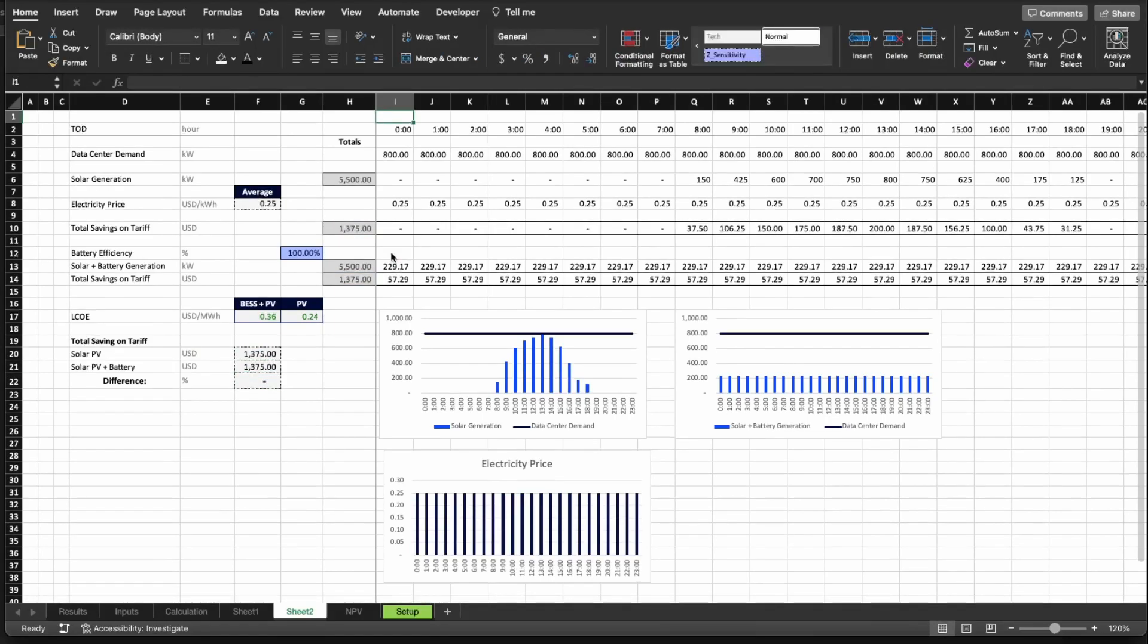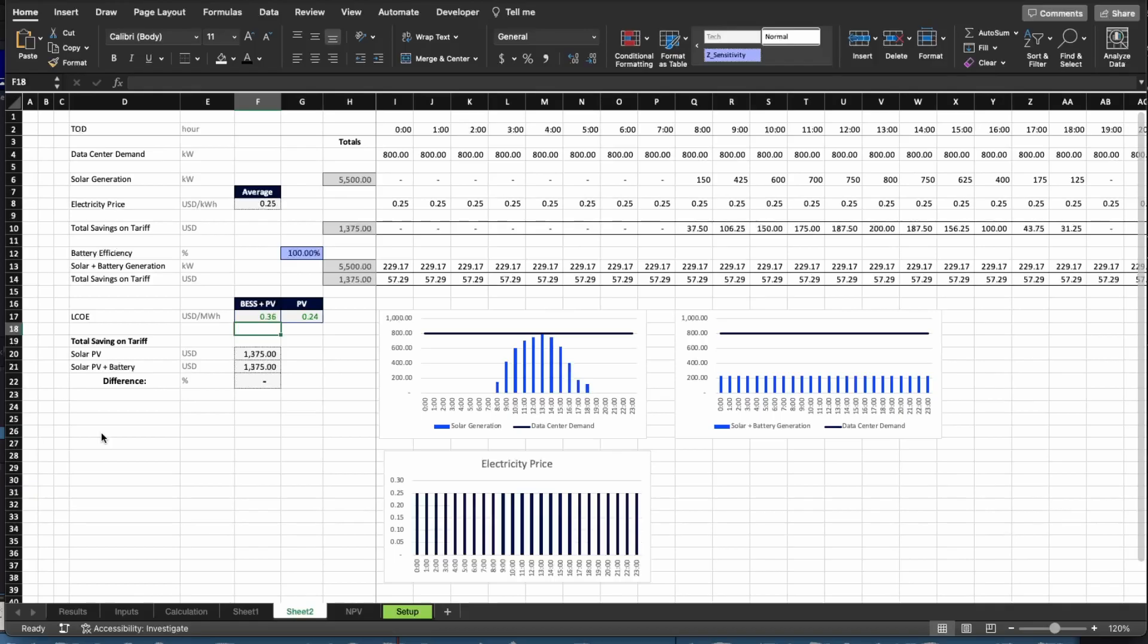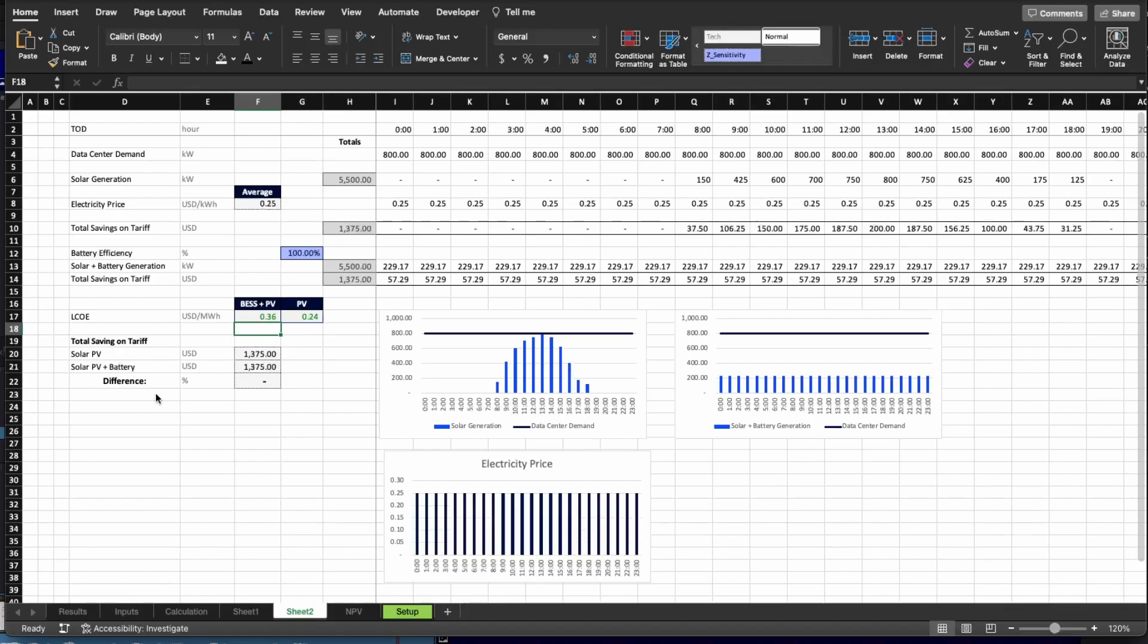So the question is, based on this scenario here, do you know which system is the best? Pause and think. And the answer is yes. You do know which option will bring the most benefits to the client. Why? Because the clients are going to save the same amount of money no matter which system is chosen. Either system one or system two, the amount of saved money will be $1,375. Therefore, because the benefit is the same, you should only concentrate on the cost. And as you know, the LCOE for PV only is lower than the LCOE for the PV plus battery.